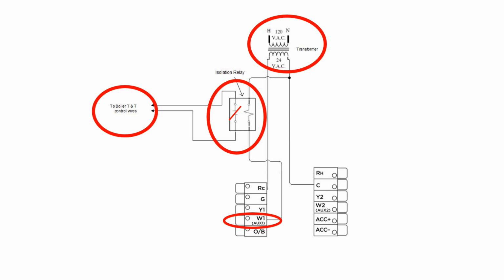Like I said, this is usually done where the control on the boiler exceeds the amp draw or the voltage rating of the thermostat or the transformer that is being used in this application. This isolates the boiler from that circuit and allows it to operate with the existing transformer and thermostat.